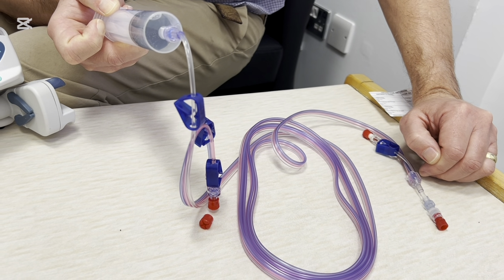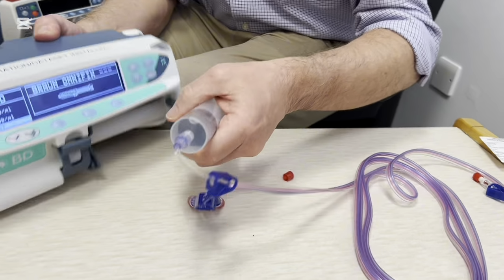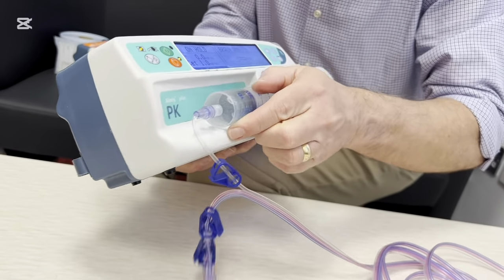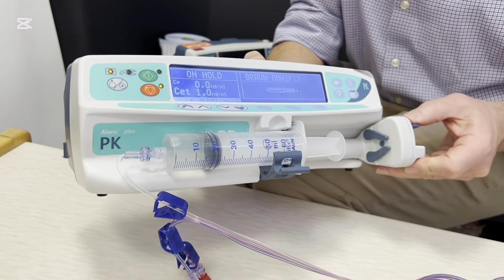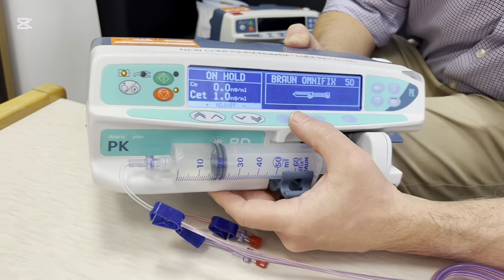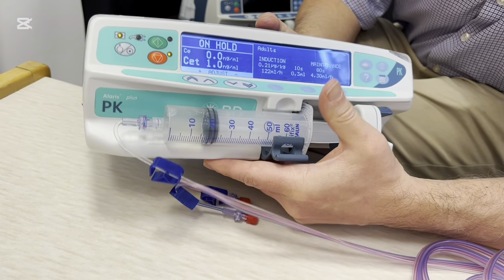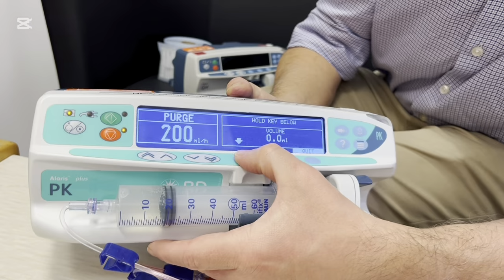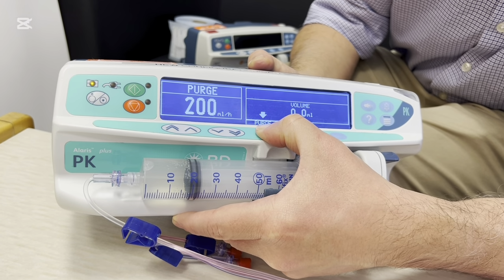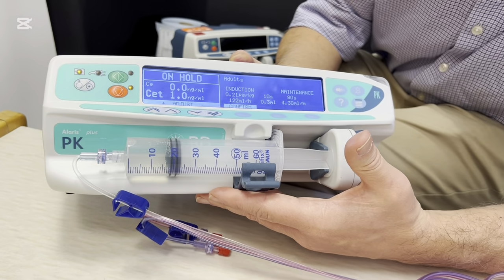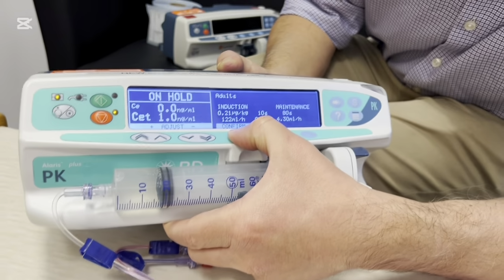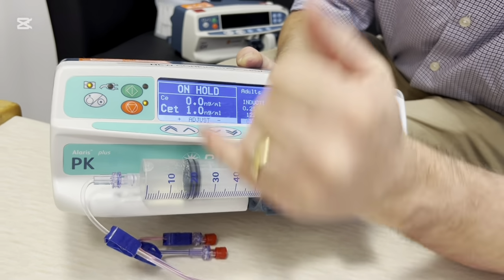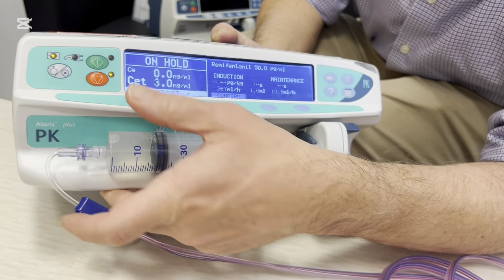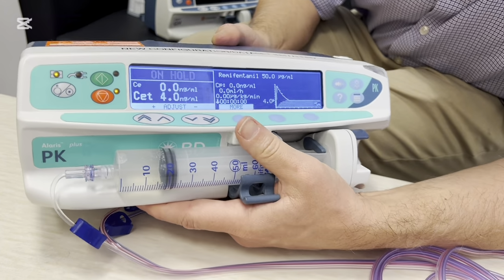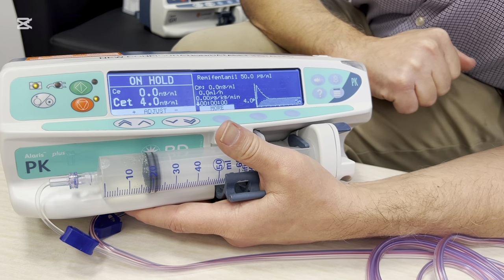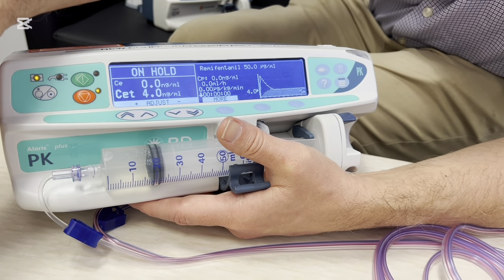So if you want to prime the lines without it being hooked up to the patient, place the syringe in the syringe clamp, slide the plunger up. So we're going to confirm that it's a B-Braun Omnifix syringe. We're going to purge the syringe just to make sure that we've taken up the mechanical slack. Okay, we've done that. And now just confirm that, so now set the target that you want. Confirm that target. It will come up with a graph that will tell you how long it will take to achieve that desired concentration.